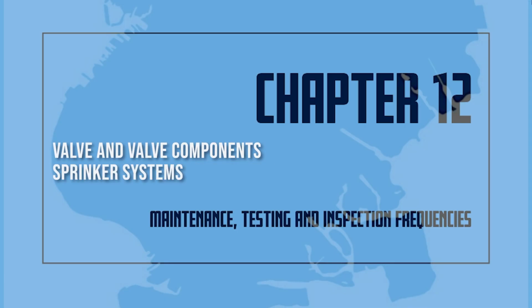Sprinkler systems. All valves shall be inspected quarterly to verify that the valves in the open position are not leaking and are in good condition, with hand wheels installed and unbroken. Downstream pressures shall be maintained in accordance with the design criteria. Hose connections. All valves shall be inspected quarterly to ensure that the hand wheel is not broken or missing, and that the outlet hose threads are not damaged and are without leaks. The reducer and the cap shall not be missing. Hose racks. All valves shall be inspected quarterly to ensure that the hand wheel is not missing or broken and that there are no leaks.